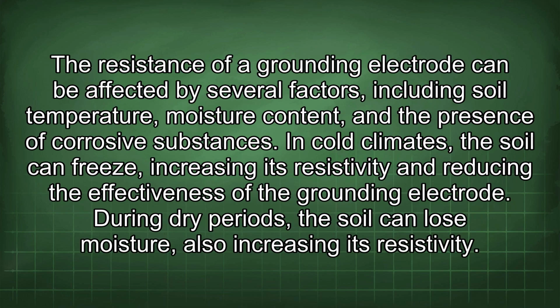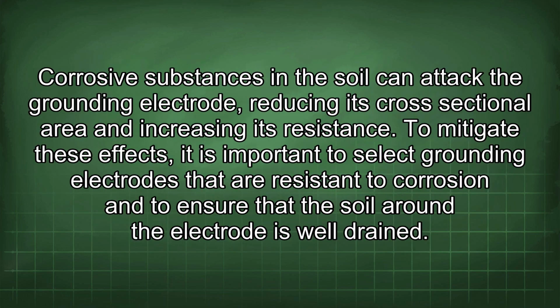The resistance of a grounding electrode can be affected by several factors, including soil temperature, moisture content, and the presence of corrosive substances. In cold climates, the soil can freeze, increasing its resistivity and reducing the effectiveness of the grounding electrode. During dry periods, the soil can lose moisture, also increasing its resistivity. Corrosive substances in the soil can attack the grounding electrode, reducing its cross-sectional area and increasing its resistance. To mitigate these effects, it is important to select grounding electrodes that are resistant to corrosion and to ensure that the soil around the electrode is well drained.